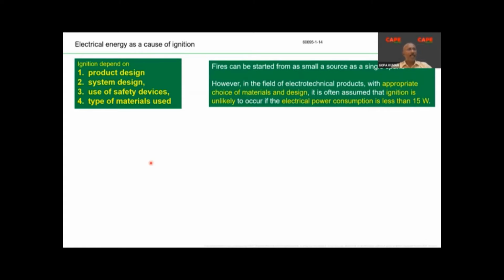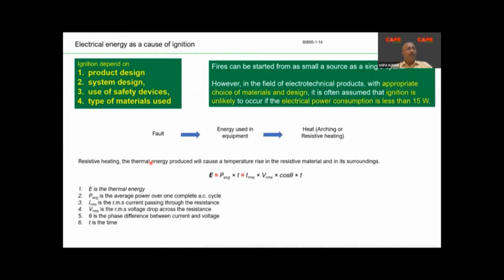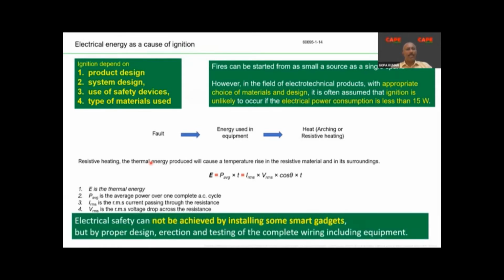But in case of an electrical equipment, the standards are made in such a way that ignition is unlikely to occur if the electrical power consumption is less than 15 watts, because the equipment is designed and tested in such a way that if the power used by the equipment is less than 15 watts, the chance of ignition of fire from that particular equipment is very much less. Now, a lot of theories, scientific research studies and scientific ideas are put into making the standards, such as what is the energy, what is the duration, what is the dissipation, and so on. Based on that, a lot of the basic electrical equipment standards are made.